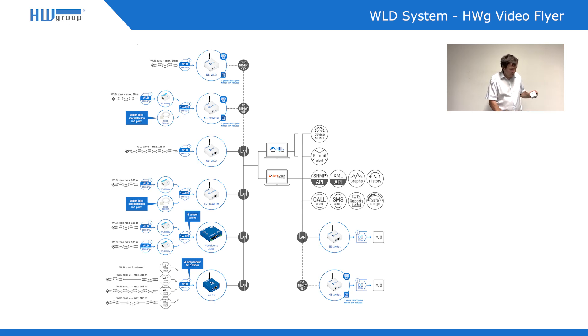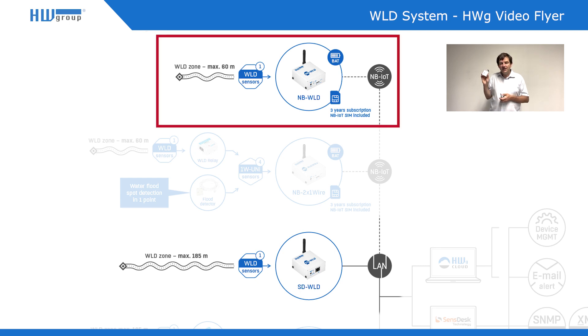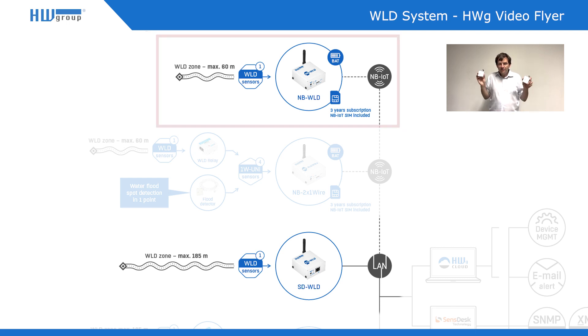The other two products are these two white devices. We call them SD-WLD and NB-WLD. Each has one zone input for one WLD zone. The difference is that SD-WLD has an Ethernet output and NB-WLD has an NB-IoT network output with its own SIM card. The NB-WLD has a battery inside, so it doesn't need to be connected to the power network and can be installed anywhere with signal coverage. Both of these are IoT monitoring devices, meaning they must be connected to a portal — either the HWg cloud, which is free, or SensDesk.com, which is paid and supports SMS and call alerts, or any other portal from our portal providers.